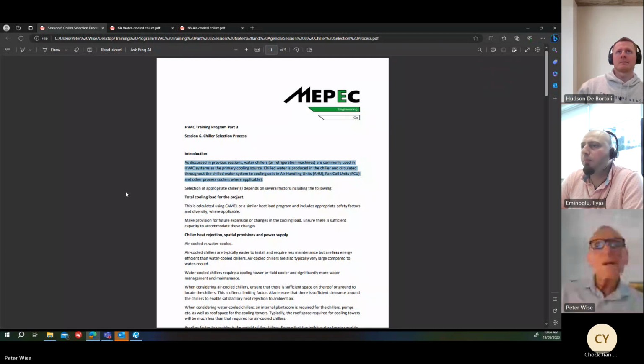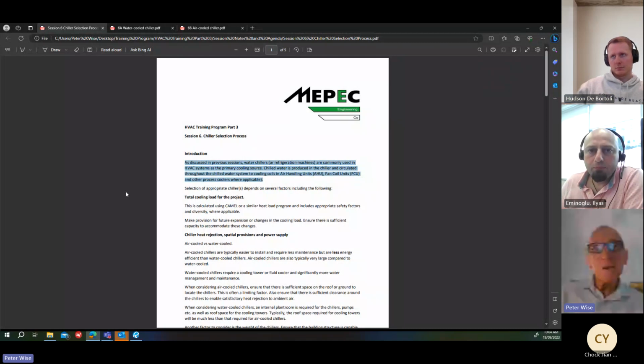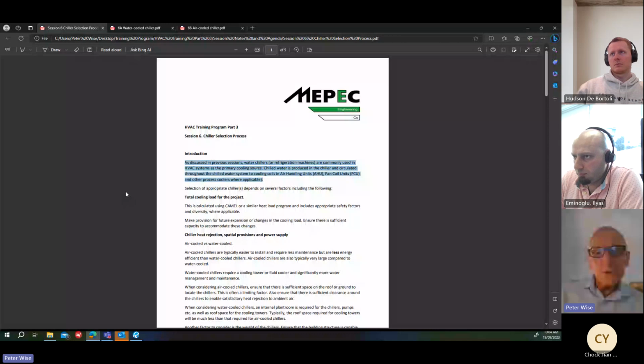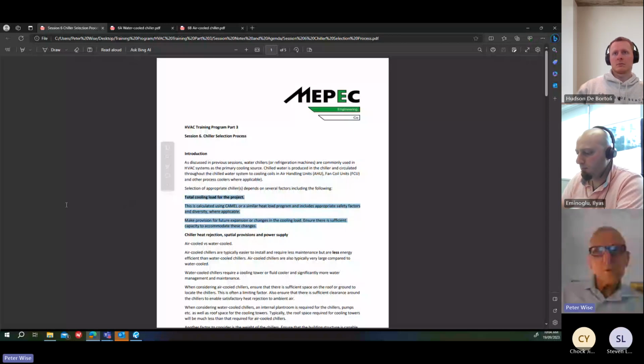Thanks. All good. Yeah, MRI machines usually need chilled water for cooling, but sometimes they have separate chillers for those. So we'll just go through some of the factors to consider when selecting a chiller. Obviously, number one is the total cooling load for the project, calculated using CAMEL or a similar heat load program, and include appropriate safety factors and diversity, if that's applicable. So a lot of different projects will have different diversity levels.